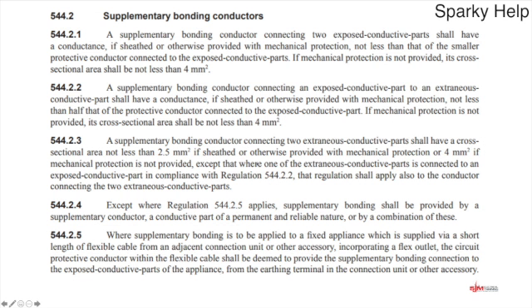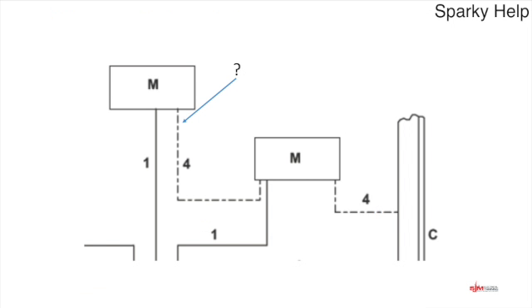So let's just have a quick look at an example, because that's the best thing to do. Between the two exposed conductive parts, we've got number 4, which is the dotted line, which is a supplementary bonding conductor, but we'd need more information. So if what we're saying is it is a 1.5 and a 1.5, well, if we look back at the previous regulations, you can skip back, have a quick look, or open your book and have a look yourself. And hopefully what you might find is that you could get away with a 2.5 with mechanical protection, or a 4mm without mechanical protection. Now if we look, then it is a 4mm and a 4mm.